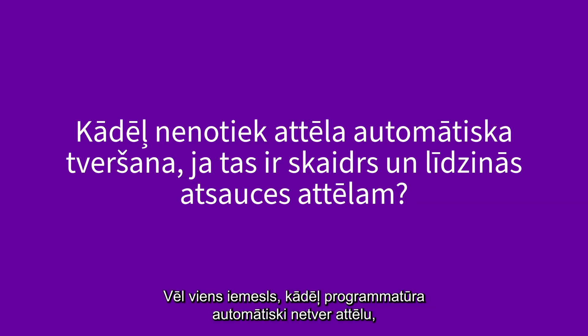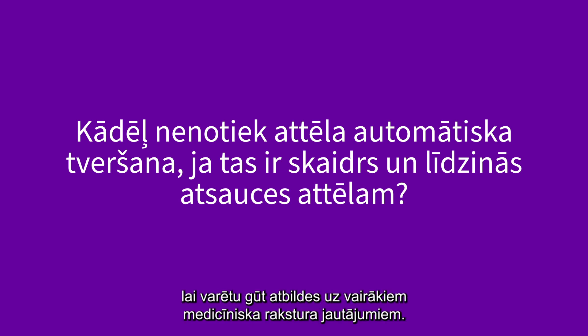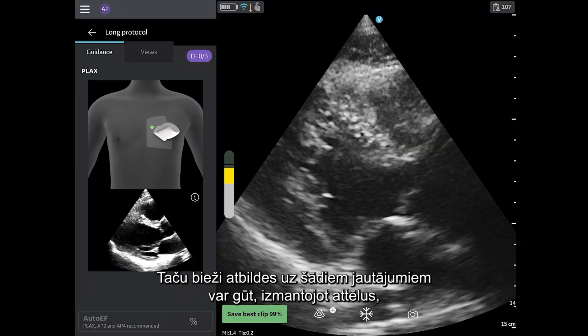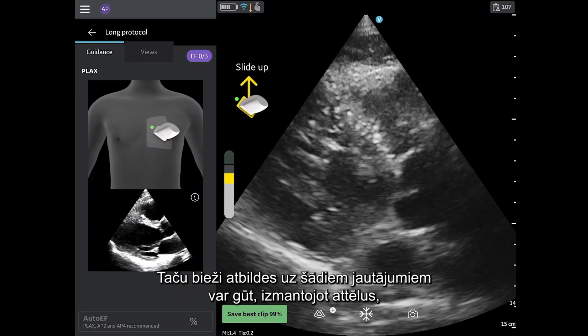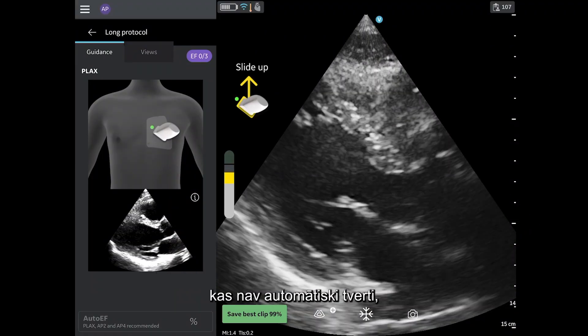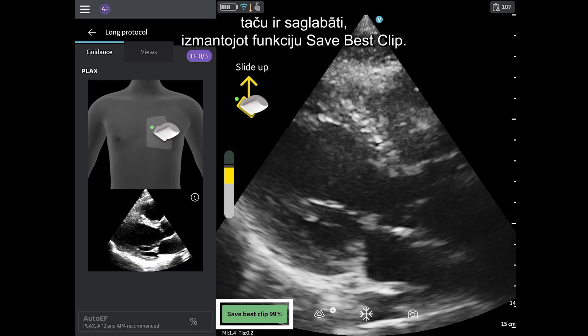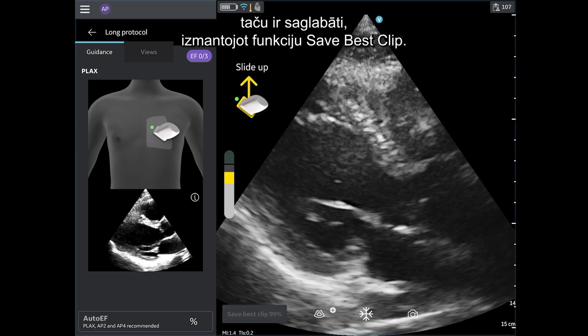Another reason why the software may not be auto-capturing the image is due to the high standards the algorithm places on image quality to allow for multiple clinical questions to be answered. However, often these clinical questions can be answered with images that do not auto-capture, but instead are saved using Save Best Clip.